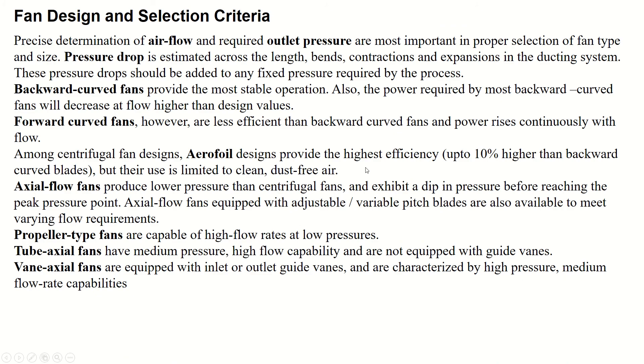There are important points in fan design and selection criteria. A fan is selected based on its airflow and outlet pressure. After calculating pressure drops in the piping and ducting systems, these should be added to any fixed pressure required by the process. Backward curved fans offer the most stable operation, and their power requirement decreases at flow rates higher than design values.